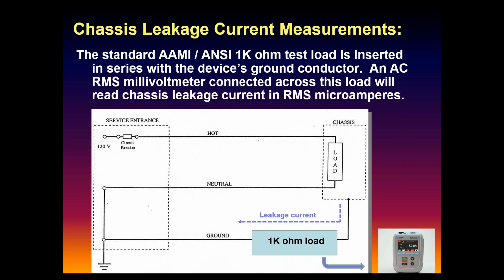This is how we simply measure it. When you plug your device into the analyzer, you're essentially inserting a standard load, which at 60 hertz looks like a 1 kilo-ohm resistor. We're simply inserting that load in series with the ground, and then measuring the RMS voltage across that resistor - millivolts RMS divided by 1 kilo-ohm gives us current in microamperes.